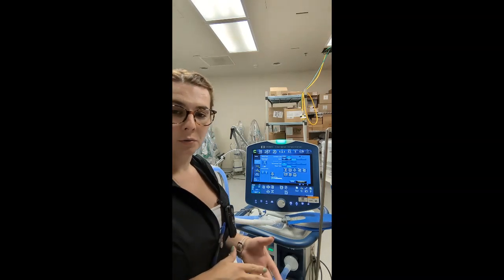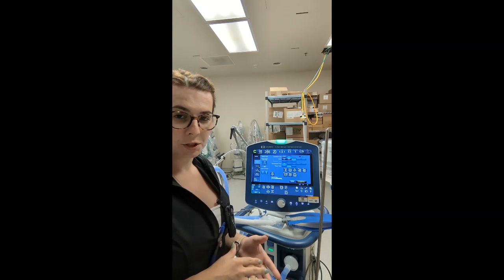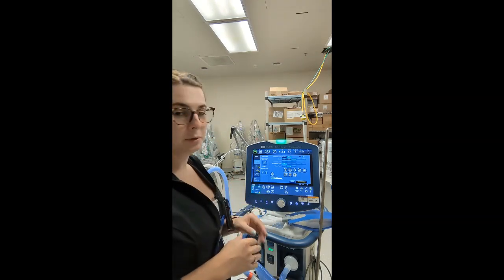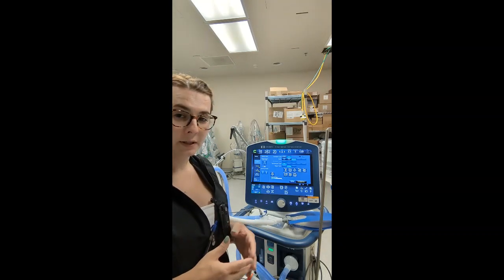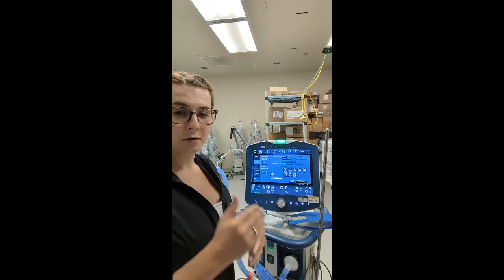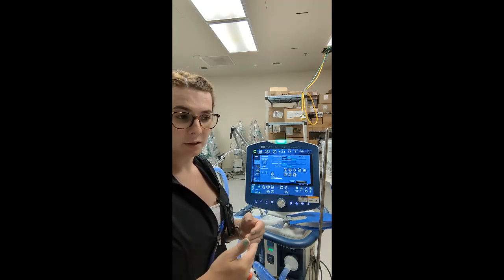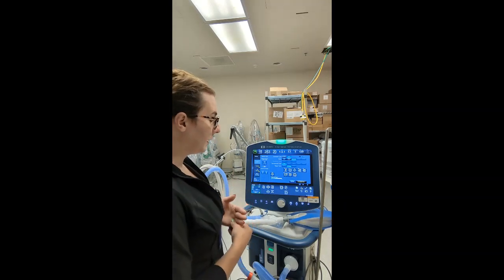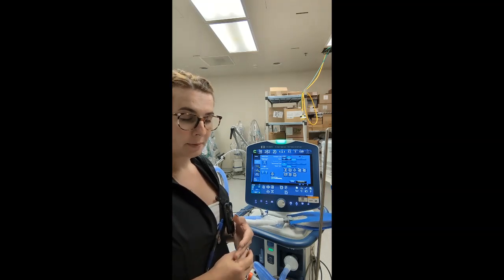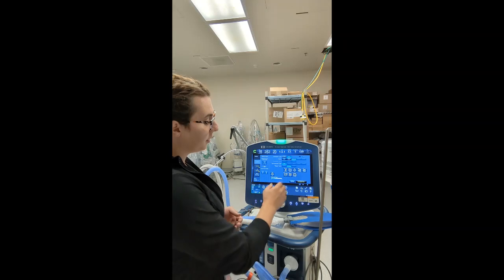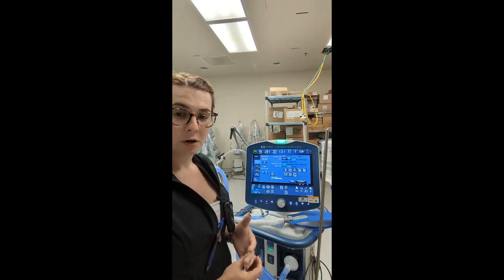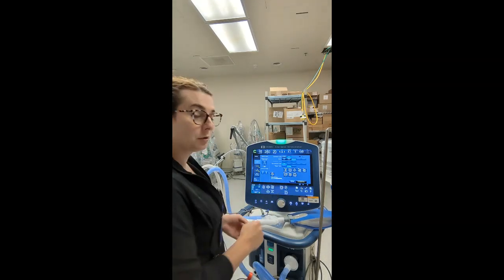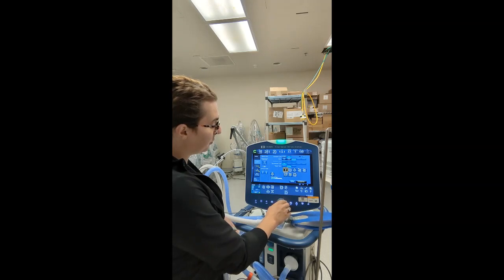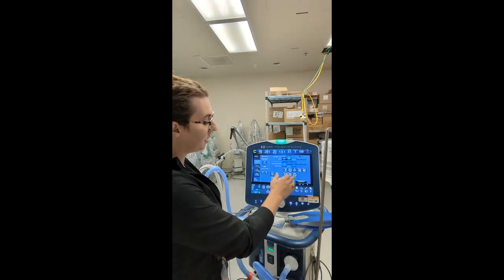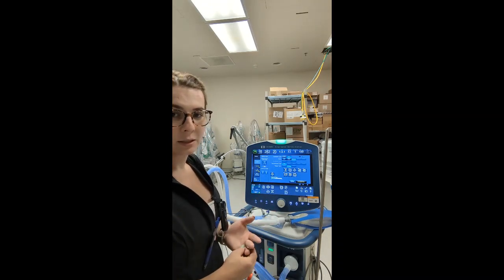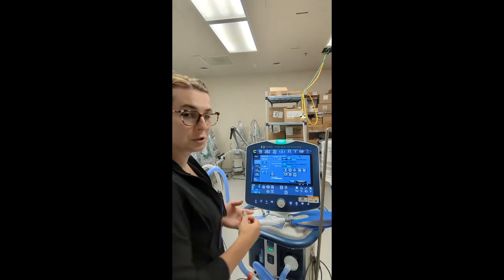One thing to note, compared to machines that are strictly built for non-invasive ventilation, our pressure support is PEEP compensated. So what that means is, unlike the V60, when you're at 10 over 5, it's measured 5 above 0 and 10 above 0. That gives you the numbers, your IPAP and EPAP, 10 over 5. On this ventilator in non-invasive mode, we get our IPAP by increasing our pressure support. Currently, we have a PEEP of 5, so our settings are essentially 5 over 5. If we want to get to 10 over 5, we would add a pressure support of 5. That means we are 5 centimeters of water above PEEP, which is set to 5. Hence, 10 over 5. And you will see this in your pressure readings.